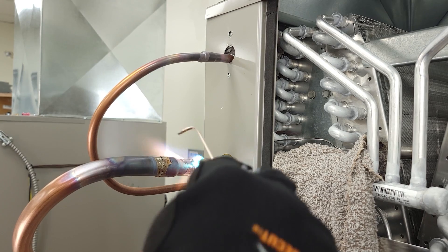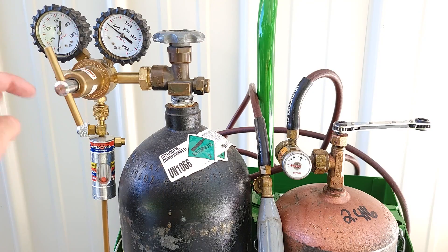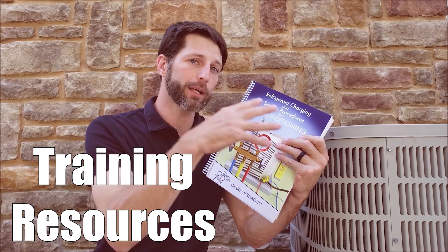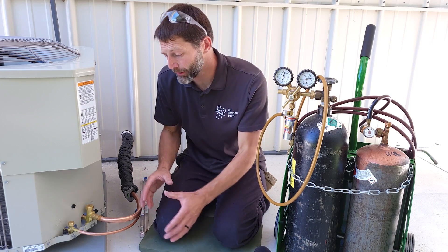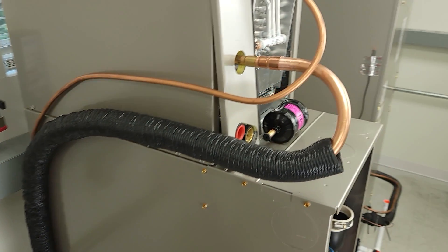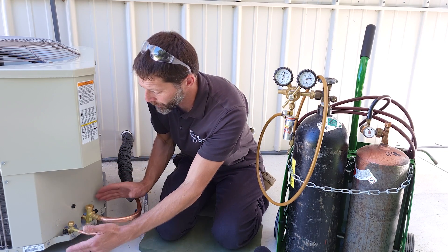In this HVACR training video, we're going over how to braze refrigerant tubing to the indoor unit and also to the outdoor unit while flowing nitrogen and using our acetylene torch. We have our line set connected to the outdoor unit and it's running inside the building and connecting to the indoor coil. We're going to wait to cut our filter dryer in and braze that in until last, and we're going to start out here at the outdoor unit.